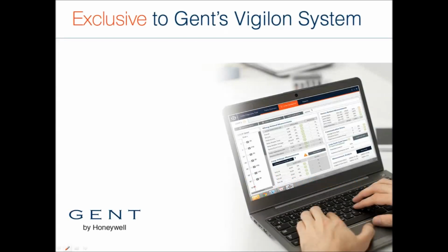The Vigilon Loop diagnostic tool and the new enhanced Vigilon Loop card provide unrivaled benefits for the system integrator and their customers. The LDT is a tool that delivers real-time data on the condition of the loop cabling and the performance of the devices it's running. Faults in the field can often be difficult to find and are a drain on time to resolve. The LDT can pinpoint problems such as loose connections or earth faults to within a few meters.